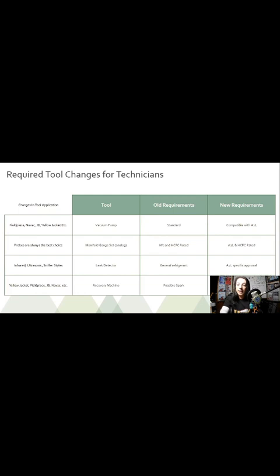Yes, those are locking caps. Those are considered locking caps, Alexander. Alexander Fagora says Supco makes caps that you can use an Allen key on, and those are absolutely acceptable as long as they are a locking cap. The only thing the locking caps are doing is preventing anybody who doesn't know how to work on A2Ls from accessing the refrigerant in the system, because if you don't know how to work on it, you shouldn't be working on it. And I think locking caps should have always been a thing. How many times have you walked up to a cap that's loose, pushing the Schrader core just right, and it's leaking all your refrigerant out?